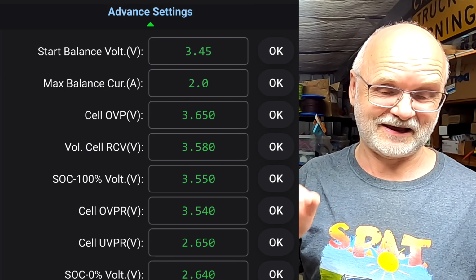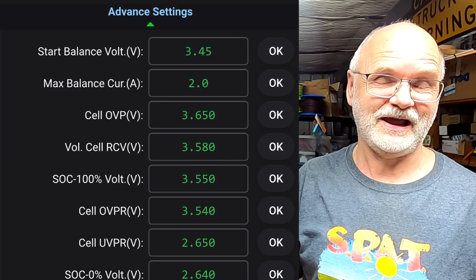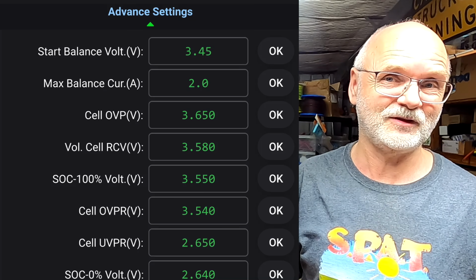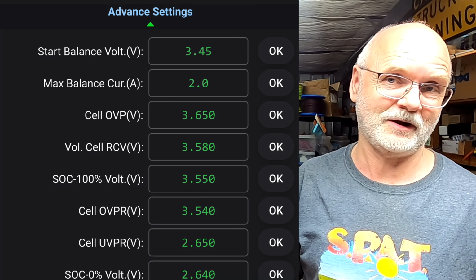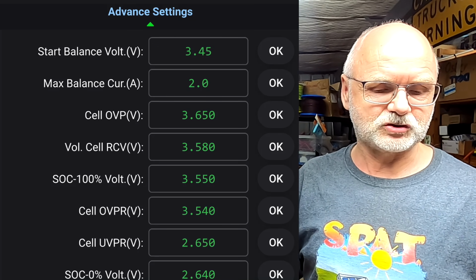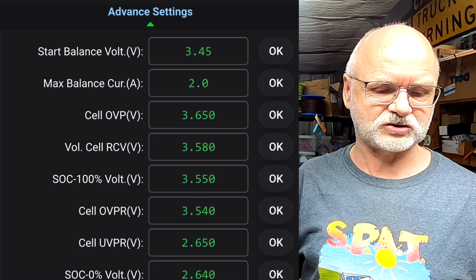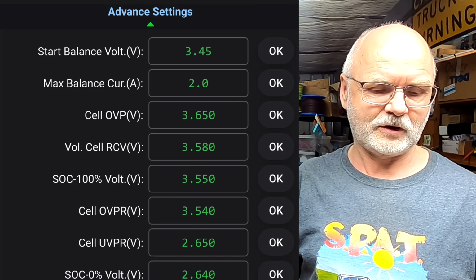So I can now set a specific voltage and reset the BMS to have the inverter and the BMS both showing 100%. Then we've got the usual stuff, the cell over voltage protection recovery at 3.54 volts.